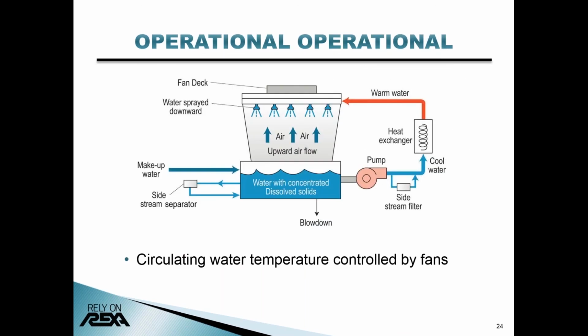This next slide shows a cutaway of a typical cooling water circuit, also known as circulating water. The system starts in the basin at the bottom of the cooling tower. Water is pumped to the heat exchanger, or in this case, the condenser, absorbs heat, and then goes back to the cooling tower. You can see water is sprayed downwards against the air moving upwards, sucked in from the sides of the cooling fans. It is here that water can evaporate and drift up through the fans away from the cooling tower. Makeup water must be continually added to the basin due to this phenomenon. An important fact to remember is that circulating water temperature is actually controlled by the cooling fans.